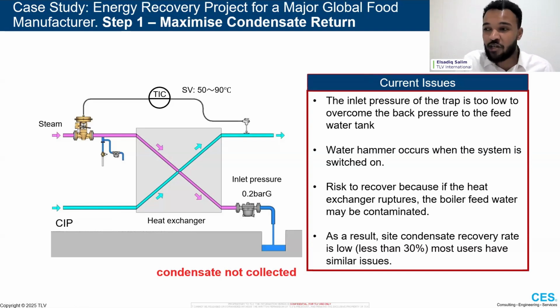And as a result, we get condensate backing up into the heat exchanger, which is unacceptable. The site needs that heat exchanger to work. They cannot accept condensate backing up, so they'll open a bypass valve, and instead of returning that condensate, it'll be dumped to the ground. Very common situation. From a process perspective, that's absolutely fine, because at the end of the day, they need that heat exchanger to work. But we need to highlight the energy loss associated with that.